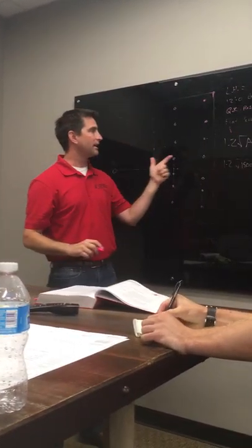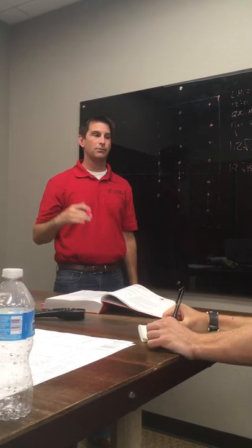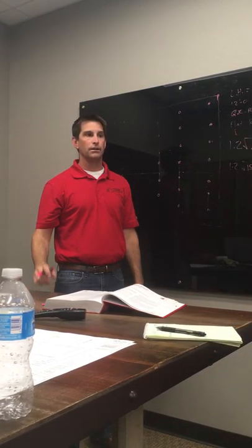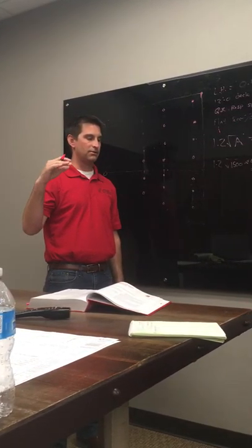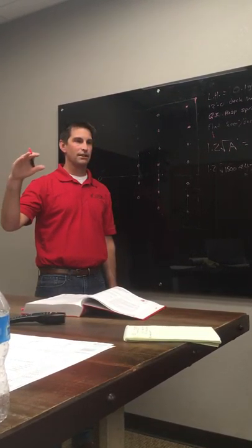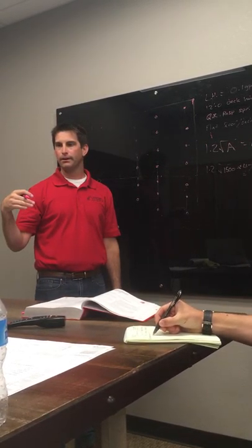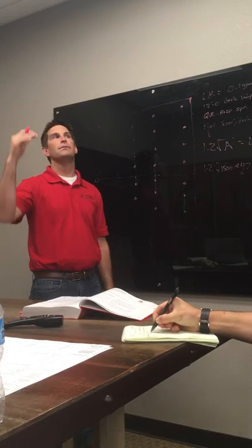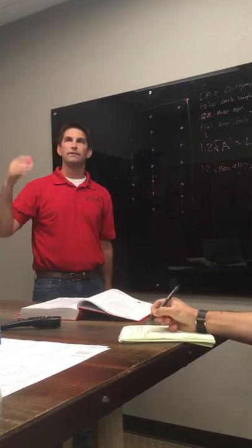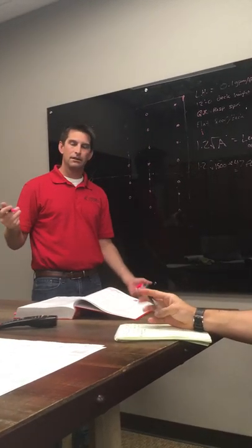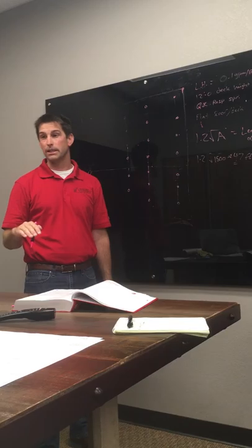The other thing it takes into account is my ceiling height. All right? It says, well, if you have a lower ceiling, you can probably reduce your area more than if you have a higher ceiling. And at some point, let's say 20 feet, for instance, once I get above 20 feet, I can't do a reduction anymore, right? And they also said, well, at some point when you get so low, it doesn't make a difference, right? If it's an 8-foot ceiling or a 10-foot ceiling, it's not going to really matter. It's going to go off so fast. So they actually limit your reduction too.